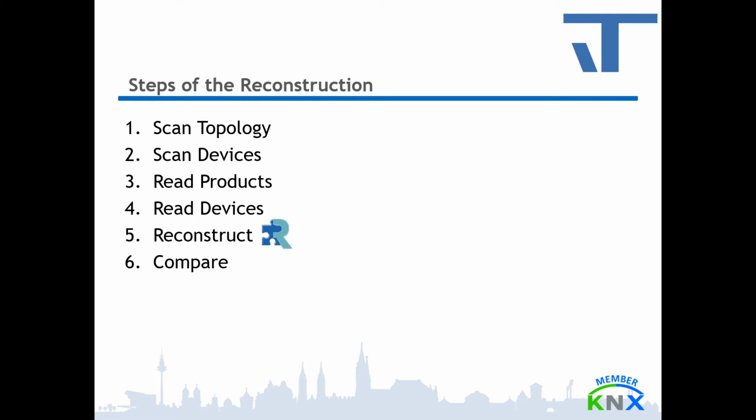Reconstruct updates the ETS project based on the read data. Adds group addresses, areas, lines, and devices into the ETS project. For each device, it calculates a parameter configuration that fits to the read download image and updates the parameter values in the ETS, sets the flags of group objects, and links the group addresses.